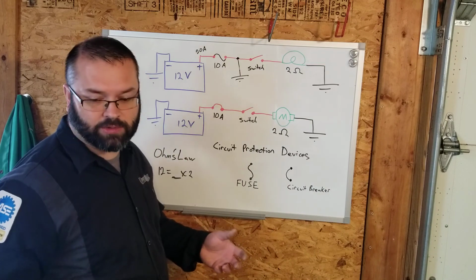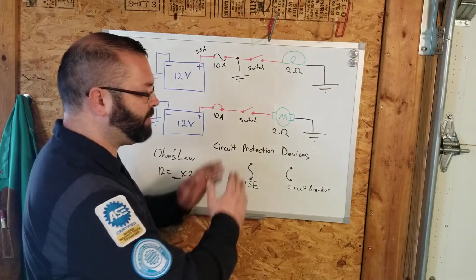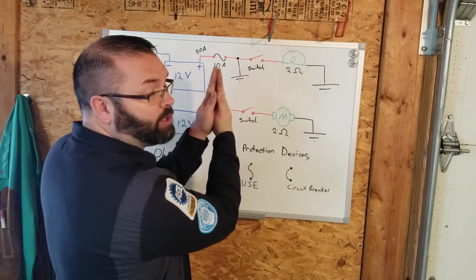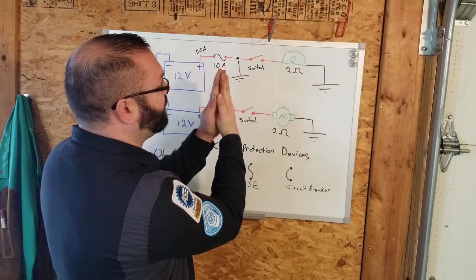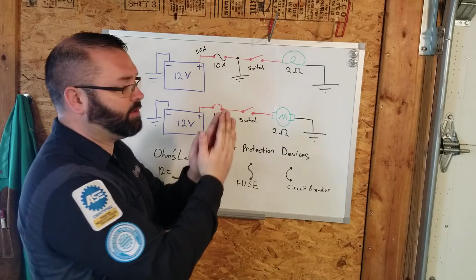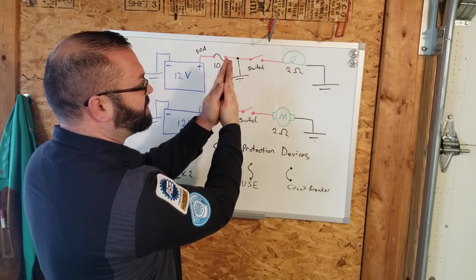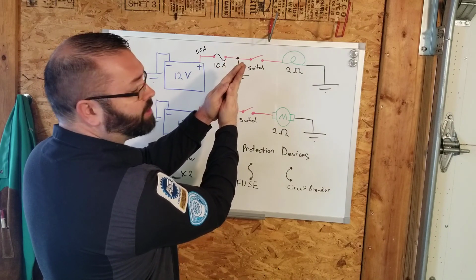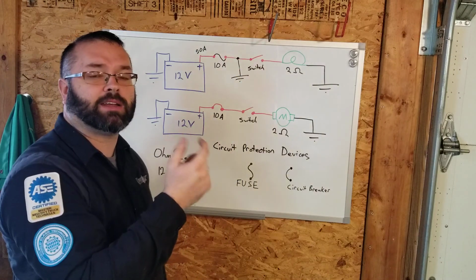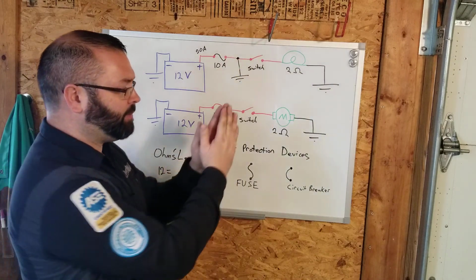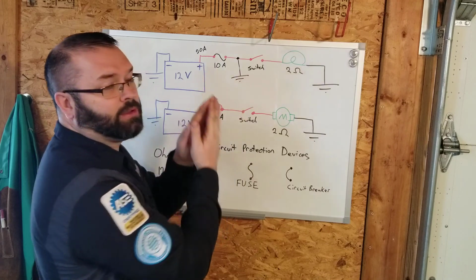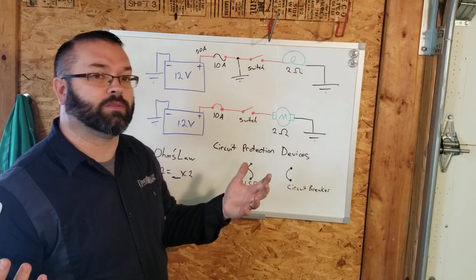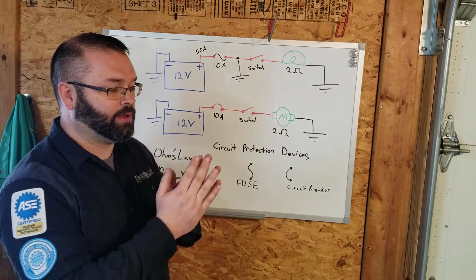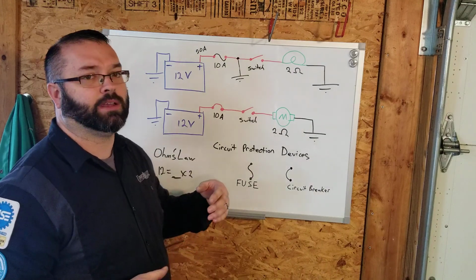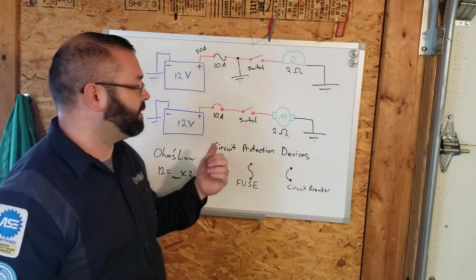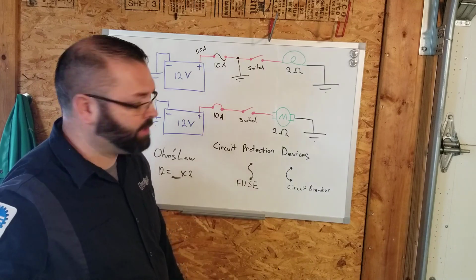What they have going on inside of a circuit breaker is they've got 2 pieces of metal attached to each other, and they're 2 different types of metal, and they heat up. As things heat up, they expand. Since the two pieces are different metals, one expands more than the other and it arches. When it arches, it breaks contact inside the circuit breaker, so it heats up, flexes, opens up, and there's no more current flow. That unit will cool down over time, make contact again, and if there's still a short or overload, it will break contact again.